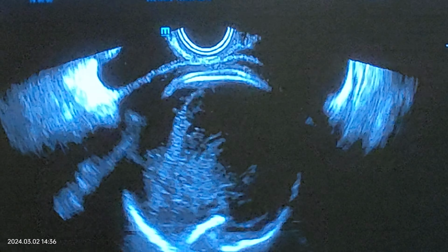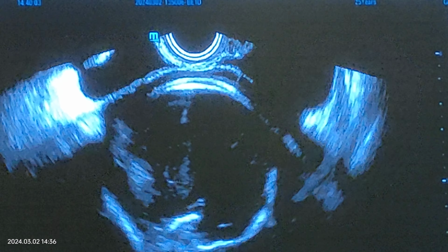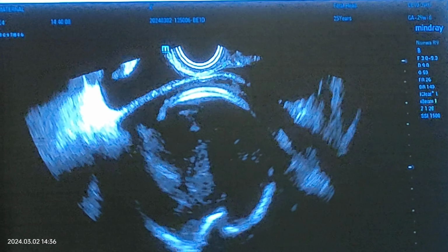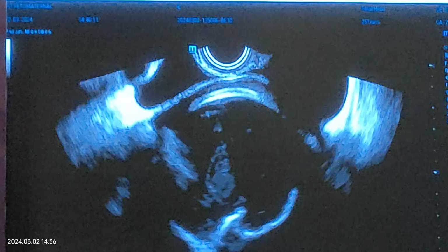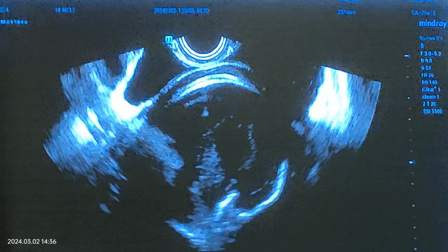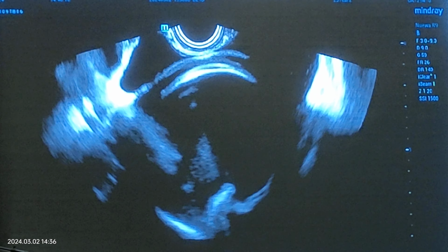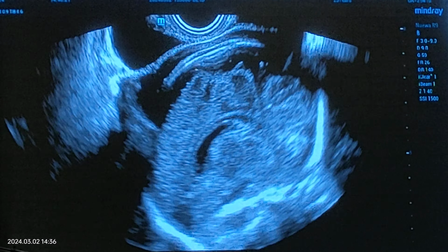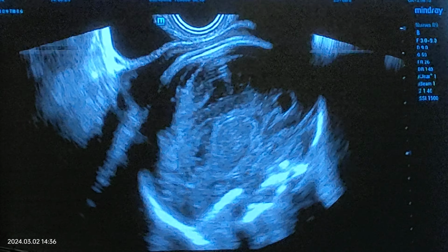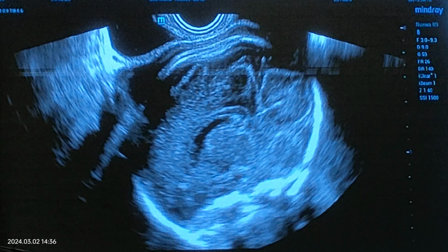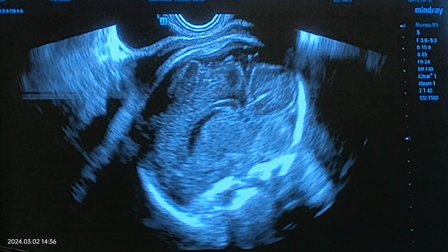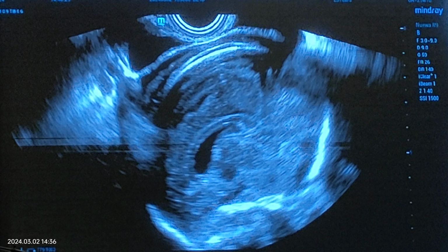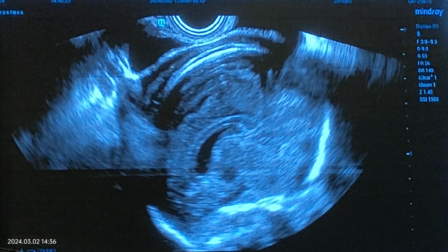So what I'm doing is, can I have this closer to me? This is a two-person scan, but normally I have my own team to press all the buttons. You see my left hand completely on the abdomen of the patient, and my right hand is holding the transducer. Now you can see this baby is running away from me, but you can appreciate the sagittal plane. Freeze. Basically, I don't have an extra hand, so this is a call for a voice command, please, a freeze voice command.